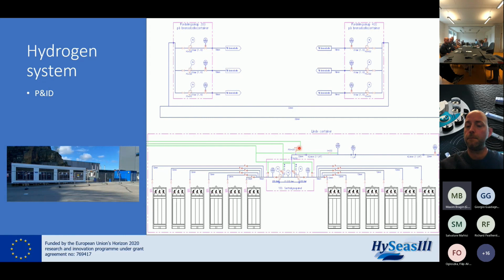Do you isolate individual banks of cylinders, or do you just rely on one valve to isolate the whole supply side? No - the procedure is to absolutely close the system. That means all valves should be closed, all breakers disconnected, and the pressure should be released to below fuel gas pressure, so we're sure it's not trying to go through the reduction valves to the fuel cells to supply them with hydrogen. That's what we saw happen because of the leakage rate of the reduction valves.